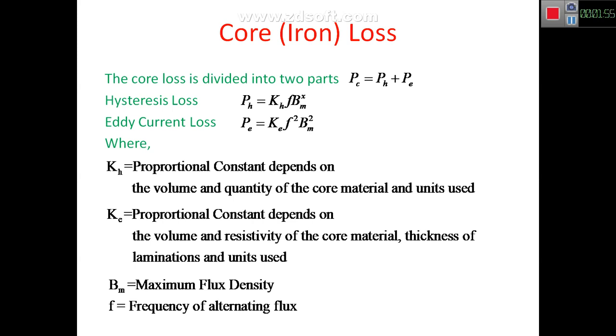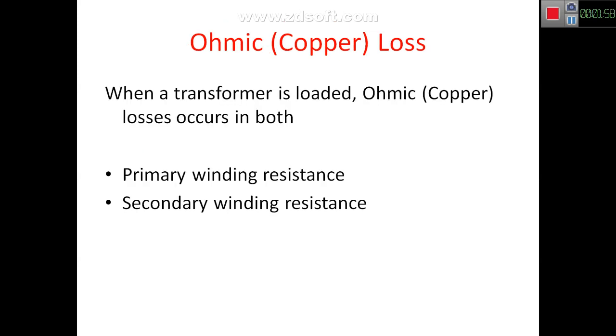The next loss is ohmic loss. Ohmic loss, also called copper loss, is the I squared R loss. There are two resistances in a transformer: the primary winding resistance and the secondary winding resistance. When current flows through the primary it is I1 squared R1, and through the secondary it is I2 squared R2. Copper loss is present when the transformer is loaded; if there is no load, the copper loss is very small and can be neglected.